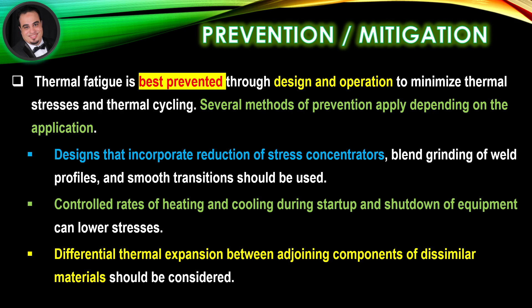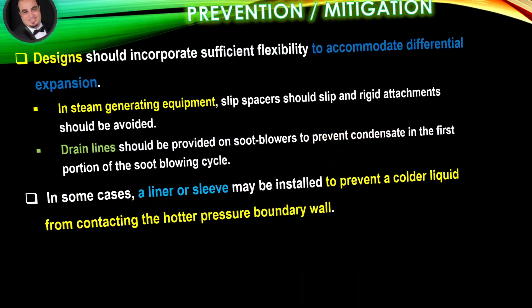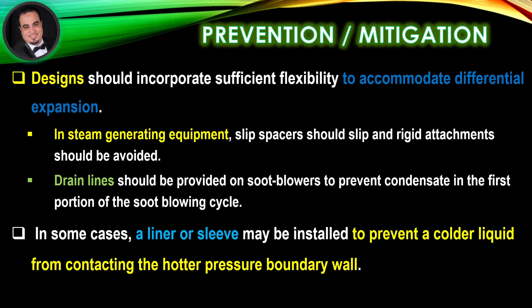Differential thermal expansion between adjoining components of dissimilar materials should be considered. Designs should incorporate sufficient flexibility to accommodate differential expansion. In steam generating equipment, slip spacers should slip and rigid attachments should be avoided.